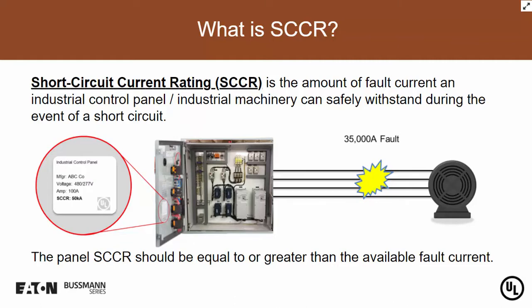If a fault occurs, and in the diagram you see the fault occurring in the conductors going out to the motor. For UL purposes, we generally consider a fault occurring either in the conductors going out to the load or in the load itself. And in this case, we have a motor, which is a dynamic device, and it's often susceptible to breakdown. So if we had a 35,000 amp fault in the conductors or in the motor being controlled by this panel, would the panel be safe under a short circuit condition? Would it be able to withstand the 35,000 amps without damage that would cause a hazard either to personnel or property? And the answer is yes, because as I mentioned, the label on the panel clearly indicates that the short circuit current rating is 50,000 amps and the fault is less than that at 35,000 amps.